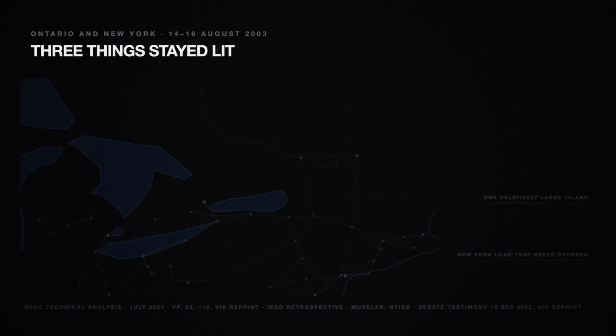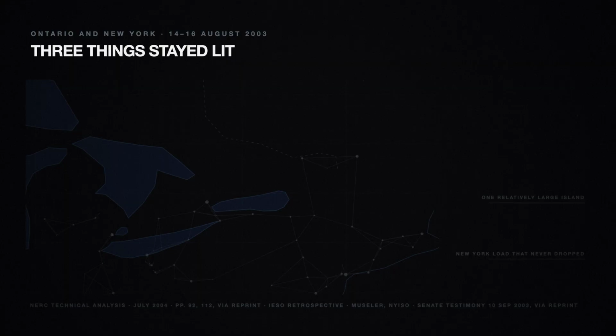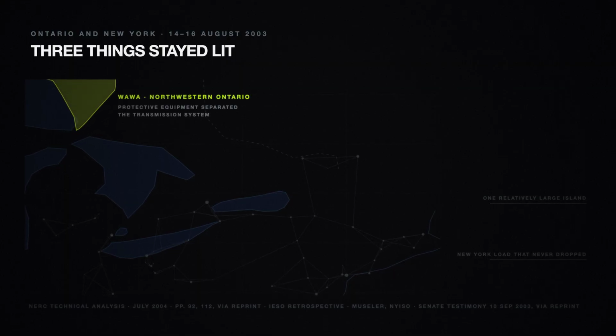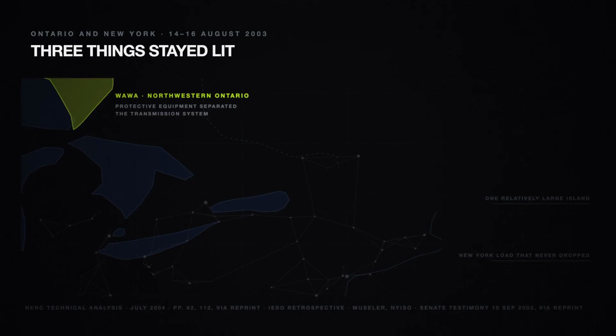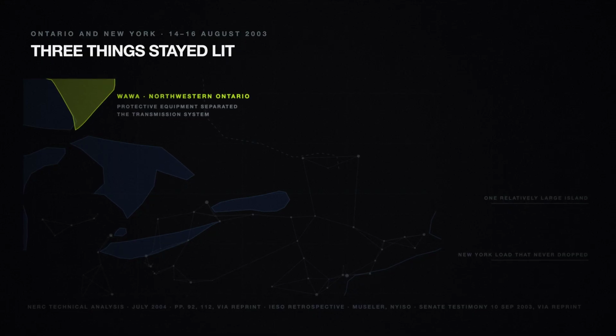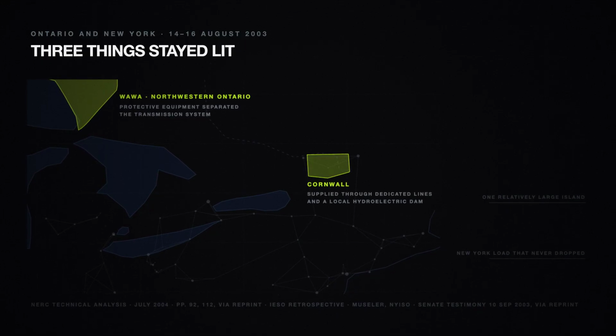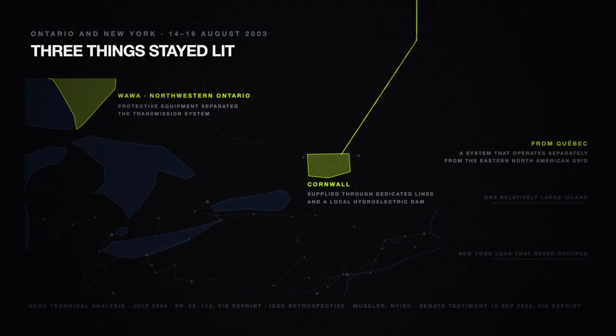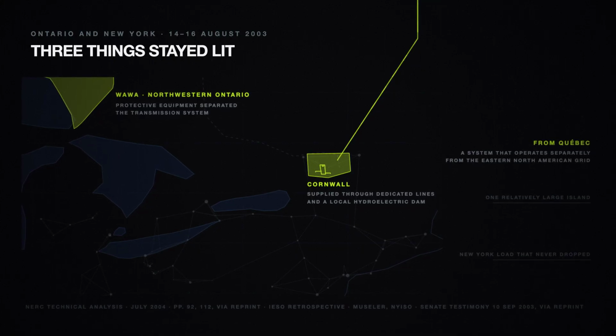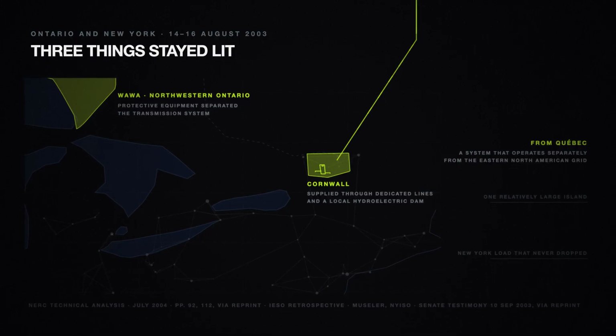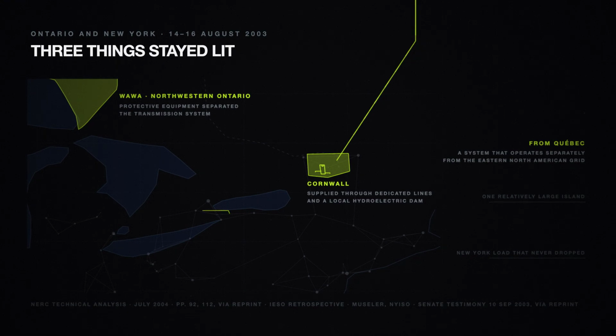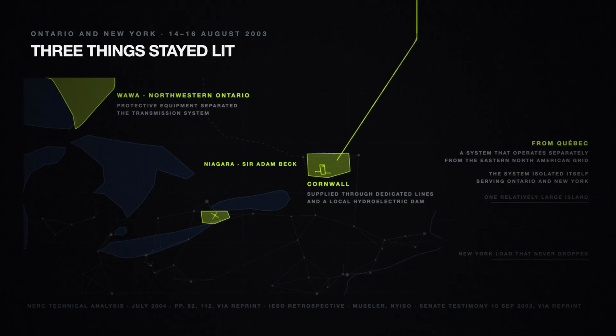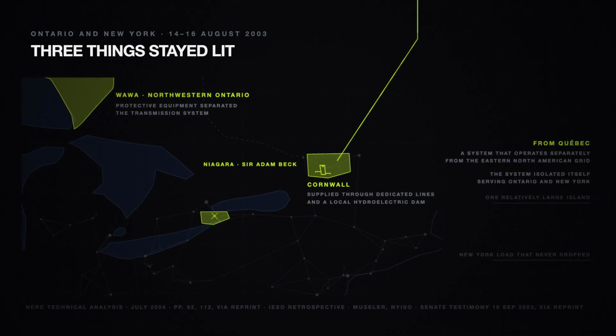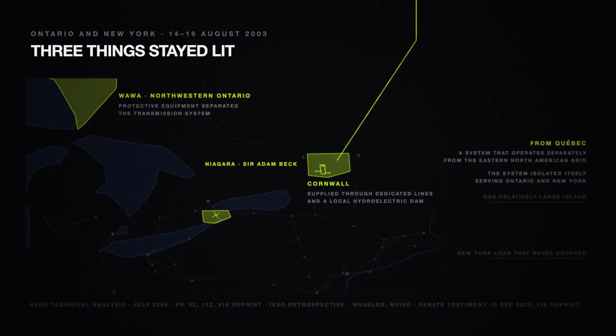August 2003. The grid fails across Ontario and much of New York. 3 parts of the system never went down. At Wawa in northwestern Ontario, protective equipment separated the transmission system and kept electricity service running in the northwest. At Cornwall in the east, power continued to flow from Quebec, a system that operates separately from the eastern North American grid, through dedicated lines and from a local hydroelectric dam. And in the Niagara area, the system isolated itself, with the Sir Adam Beck hydroelectric station serving customers in Ontario and New York, and, in the Ontario operator's words, playing a critical role in re-energizing the system.